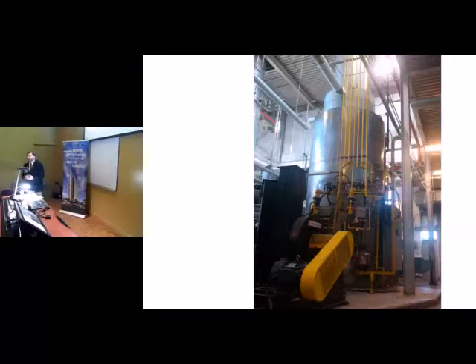What it does basically is we have two sets of boilers in the powerhouse generating energy for the campus. There's two steam boilers, two 400 horsepower steam boilers that generate steam for the remaining existing buildings, because the original campus is all on steam. So that maintains the administration building and a few other small buildings that need steam heat. We then have two brand new hot water boilers, both 400 horsepower as well, that do the hot water heating for the air terminal building. When all that equipment's in operation, we take the flue gases off those boilers, so the exhaust basically off the chimneys, and we run it through this machine over here, which I should stop pushing the wrong button.